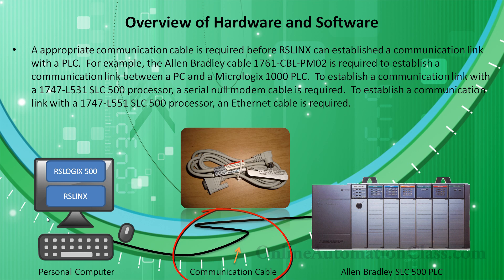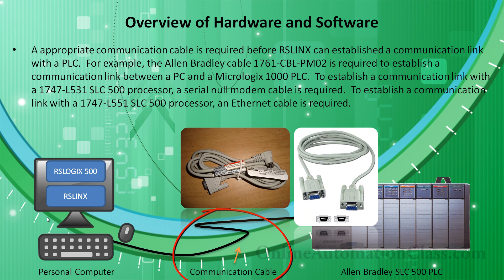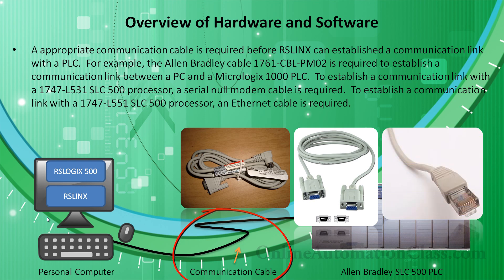To establish a communication link with a 1747-L531 SLC 500 processor, a serial null-modem cable is required. To establish a communication link with a 1747-L551 SLC 500 PLC processor, an Ethernet cable is required.